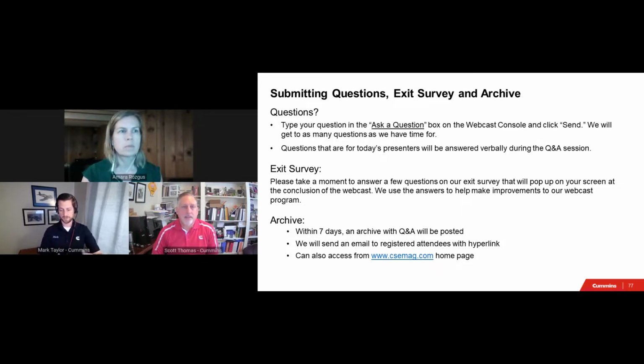With regard to the question of fuel efficiency, you probably think about this in terms of your own car. There's an optimal RPM to hit for cruising. Low RPM at your top gear is usually really efficient. It turns out for our generator sets, we're already operating at a very efficient RPM. 1800 RPM is a sweet spot for diesel and gas. And so at that point, your fuel consumption scales quite linearly with power. If you're running at 70% of nameplate load, you're probably going to be burning 70% of the fuel. So you're not going to get any efficiency gains one way or the other that way.